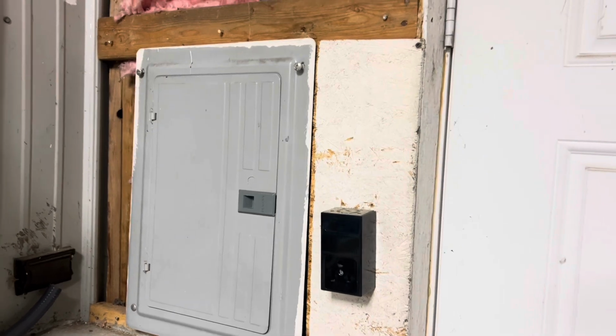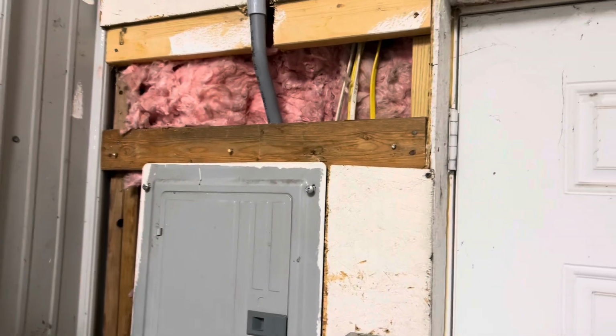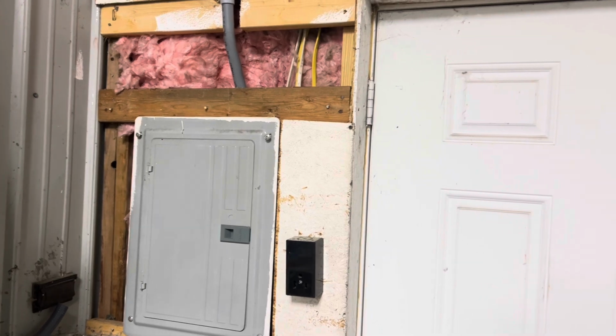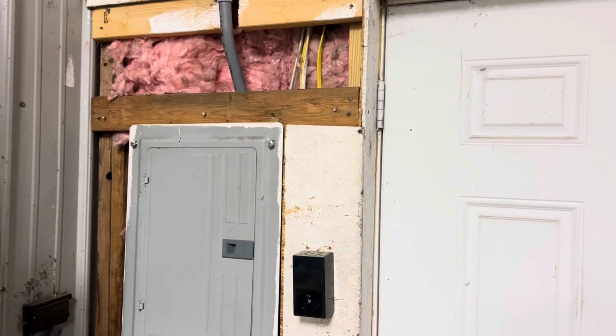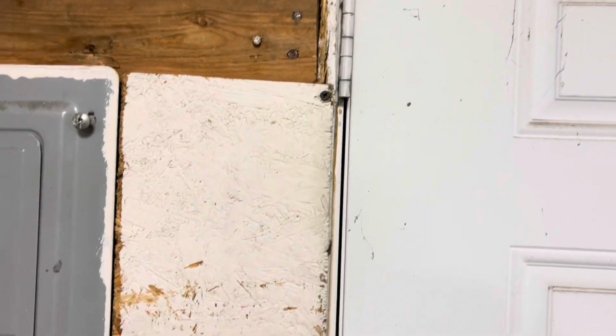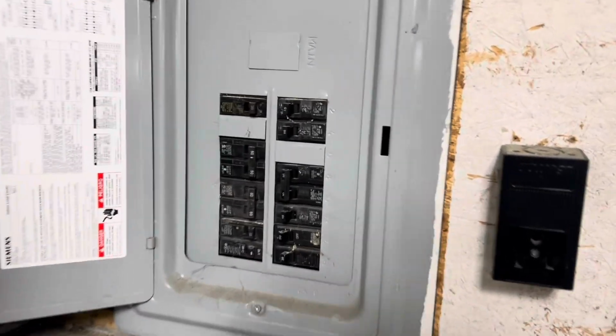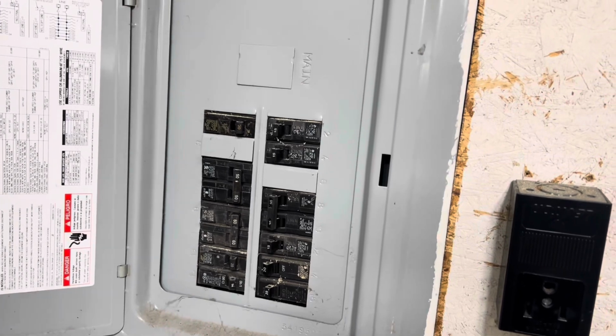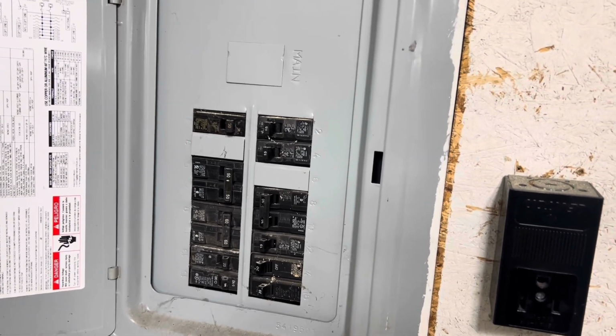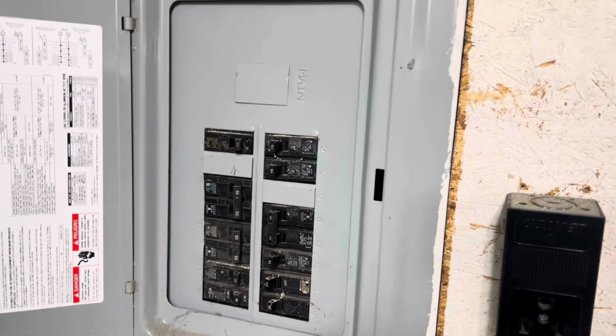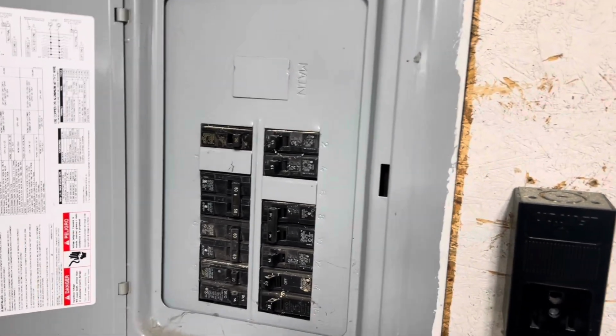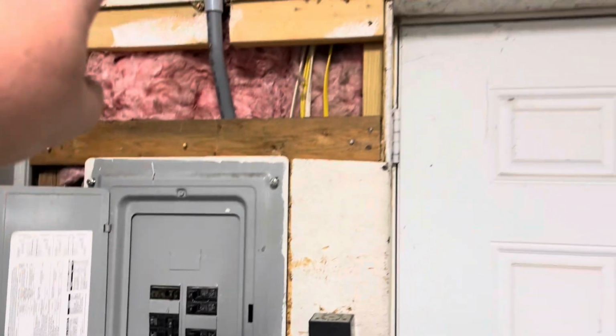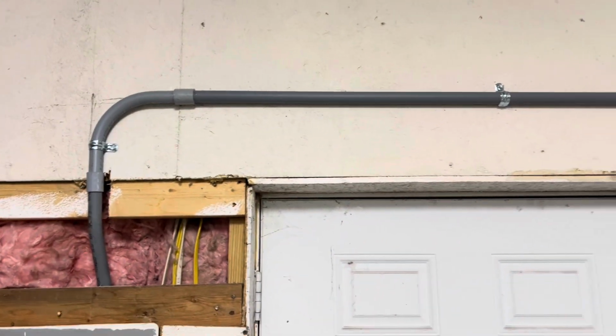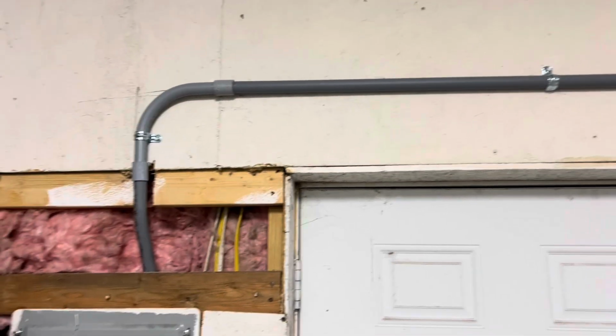First thing we had to do was come over here to the electrical panel. There was a board here before, and we had to take that off so we could access the back side of the panel. Then we needed to add a 60 amp breaker for this unit. Some units only take a 50, or a 40 or 45 will work, but since this is a 4-ton, it needed a 60. So Danny had to wire in a new circuit, and to do that we had to get the wire outside somehow.